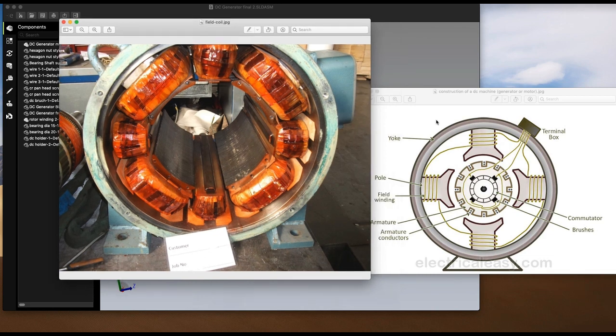Let us now identify some parts and their functions. This is the magnetic frame or the yoke. It is made of cast steel or rolled steel for large machines, and cast iron for smaller machines. The two main purposes of the yoke are: number one, it supports the poles and provides mechanical protection to the inner parts of the machine; and number two, it provides a low reluctance path for the magnetic flux.